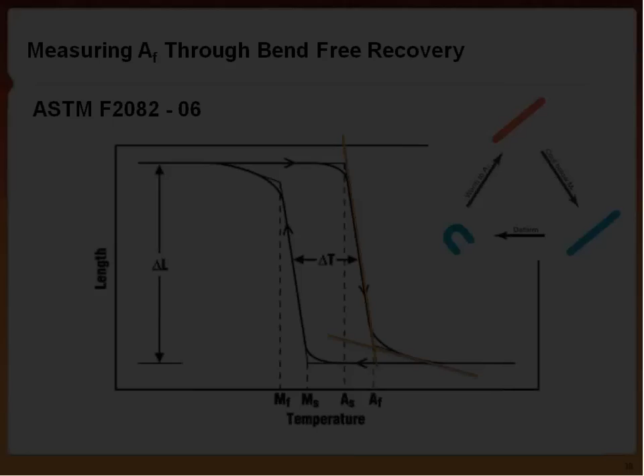So when I talked before about the differential scanning calorimetry graph and the heat flow in and out of the material, it's really not good for testing the functionality of your device. When we test the functionality of the device, we look at the ASTM standard F2082-06, which says we need to do bend-free recovery of the nitinol material. Bend-free recovery is just using nitinol's shape memory aspect. You cool it, you let it deform, and then you heat it back up.